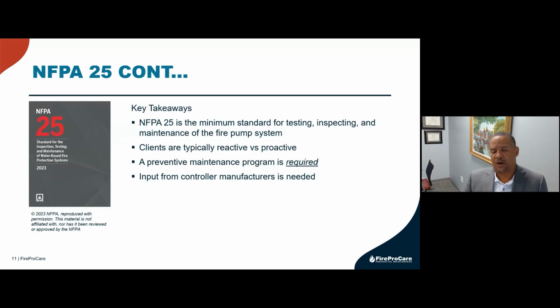So key takeaways so far when it comes to the code are that NFPA 25 is the minimum standard. Keyword is minimum for testing and inspecting and maintenance of the fire pump system. Customers are typically reactive versus proactive. It's just the way it goes. No one wants to go spend extra money, but when you react and something goes wrong, you're going to pay 10 times more than what you normally have to pay if it was properly maintained. You also should note that a preventive maintenance program is required per Chapter 8.5. Remember, Chapter 8.5 and NFPA 25, a PM program is required. And input from the controller manufacturers is needed because it's never been put out there. Those are key takeaways I want you to ride with when you leave here.